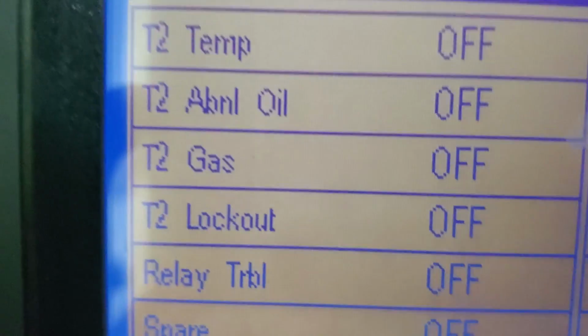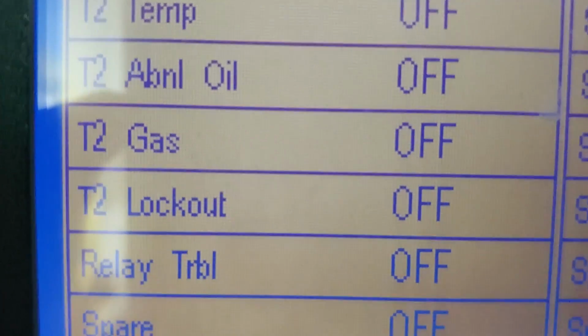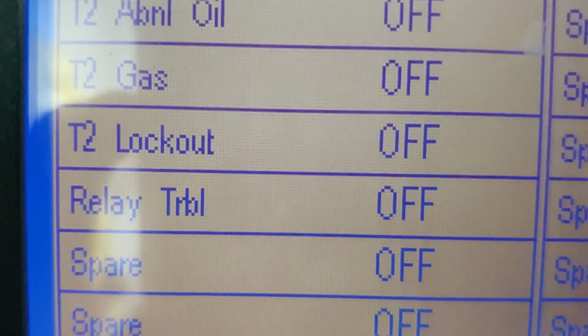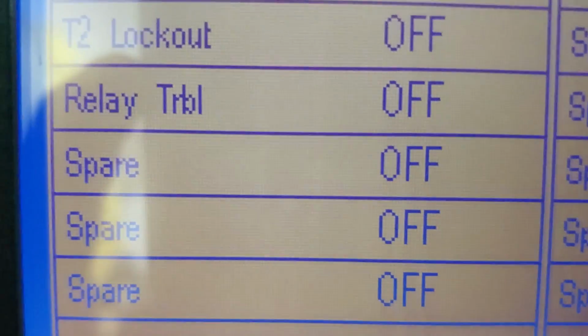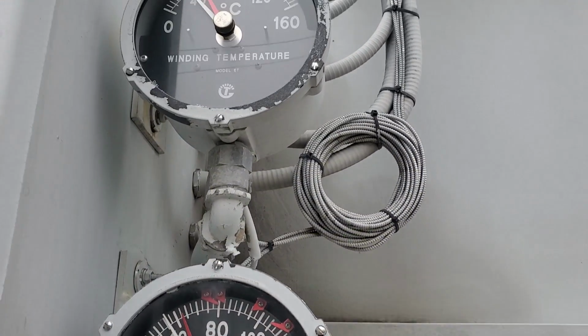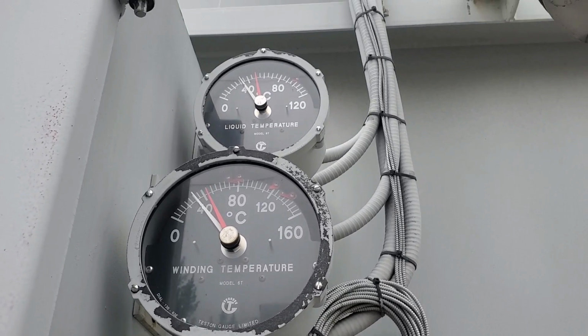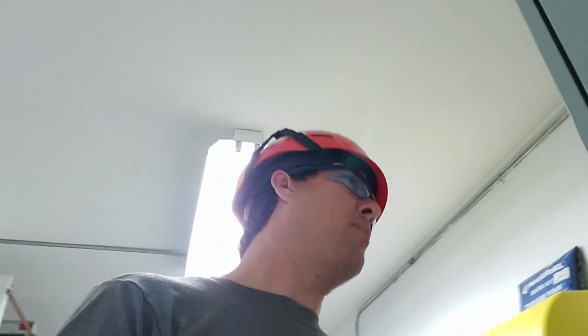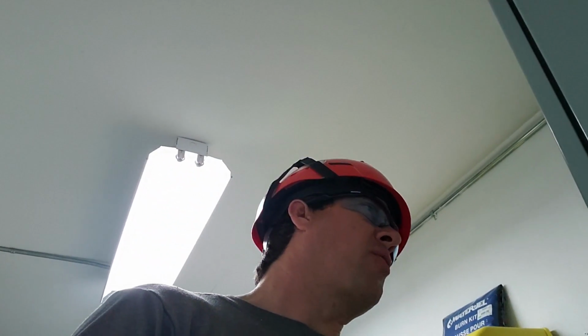Yeah, so substation alarm. So here's a few examples. We have temperature, abnormal oil, gas, lockout, relay trouble. Some of the spares are for some simple things like building temperature and stuff. There's not a whole lot of alarms on this guy here. A lot of times I can clear the alarm on my own. If there's a problem with one of the relays or in the power transformer itself, I'll call a substation tech to investigate further.